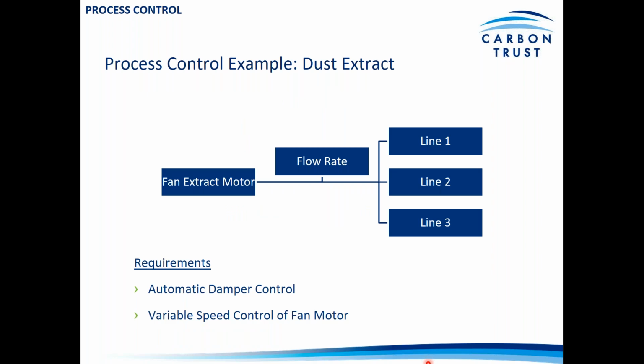Another example here that we're going to look at as a case study is process control of a dust extract system. So for a joinery works or a business of that nature, they may well be operating a number of different lines, each with extract ducts taking the dust and the wood material away. That's quite often using centralized fan motors. And it can be the case that that fan simply operates at a fixed speed. So even if the line utilization changes, that fixed speed fan might just continue to operate at the same speed. Using a variable speed fan motor, using damper control to switch off the lines when they're not required can make a significant difference in the energy performance of the system.